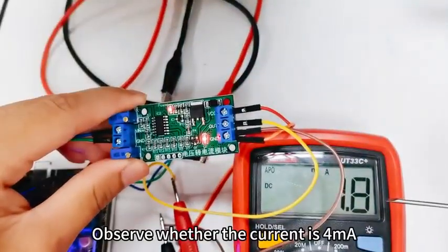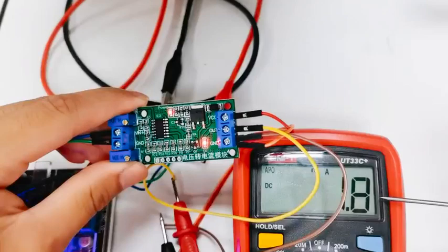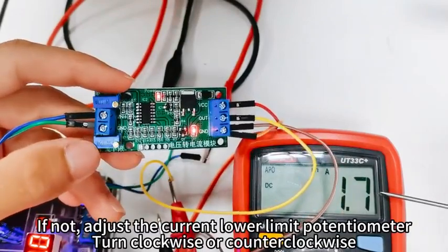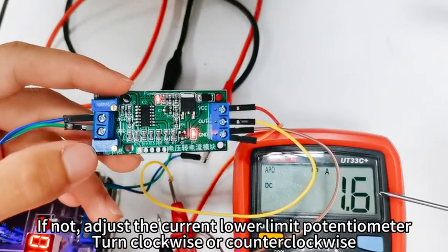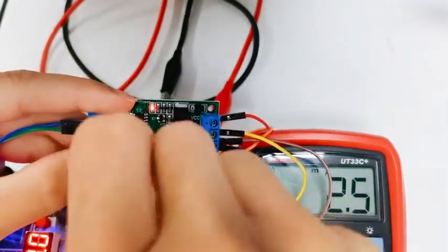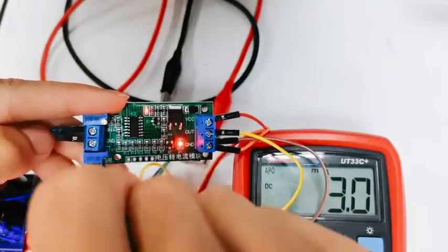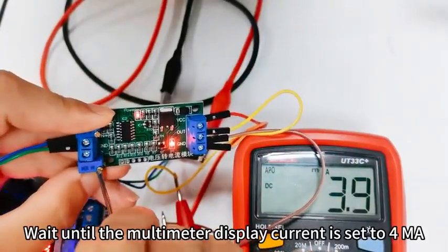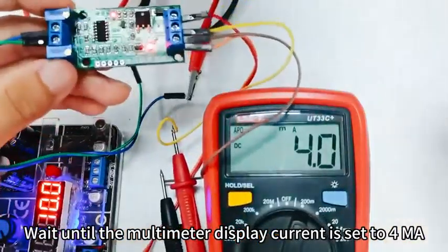Step 5: Observe whether the current is 4mA. Step 6: If not, adjust the current lower limit potentiometer, turn clockwise or counterclockwise. Wait until the multimeter display current is set to 4mA.